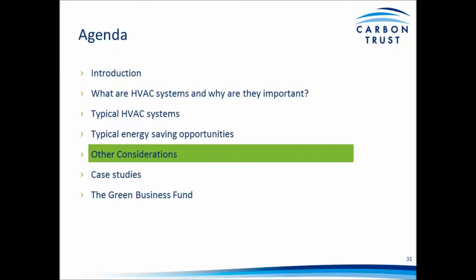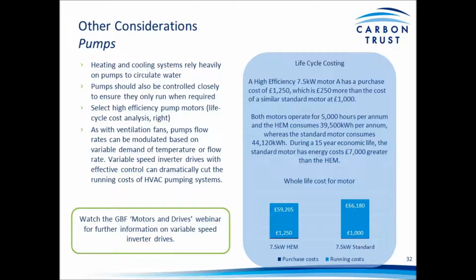Some other considerations: pumps. Heating and cooling systems rely heavily on pumps to circulate water. We often see them running 24/7 when not required, so check heating demands. So check your timer set points. Half-hourly energy consumption data can be useful for analysing where pumps are running outside of operational hours. You can also do effective life cycle costing when purchasing a pump. A lot of people don't do this. It's well worth, as this case study shows here, investing in higher efficiency pumps, as they'll often pay back multiple times during the life of the pump.